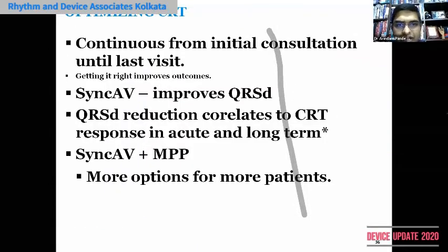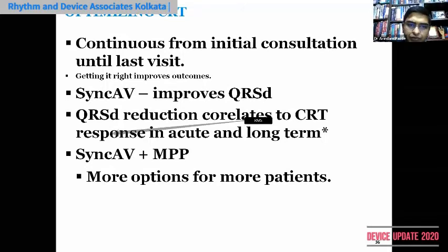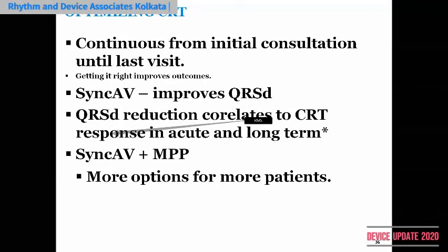Now, optimization of CRT continues from initial consultation until the last visit, very important. It's a lifelong matter. Just implantation is not sufficient. A proper programming at regular intervals has been shown in multiple trials to improve the outcome. SYNC-AV improves the QRS duration. QRS duration reduction correlates to CRT response in acute and long term. And if we combine SYNC-AV with multi-point pacing, then we can actually have more options for more patients.